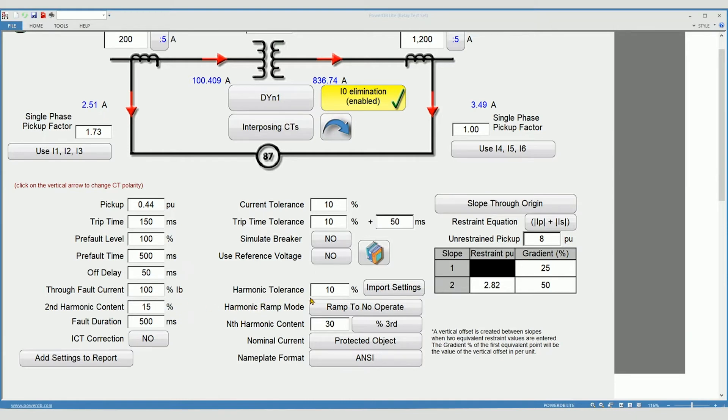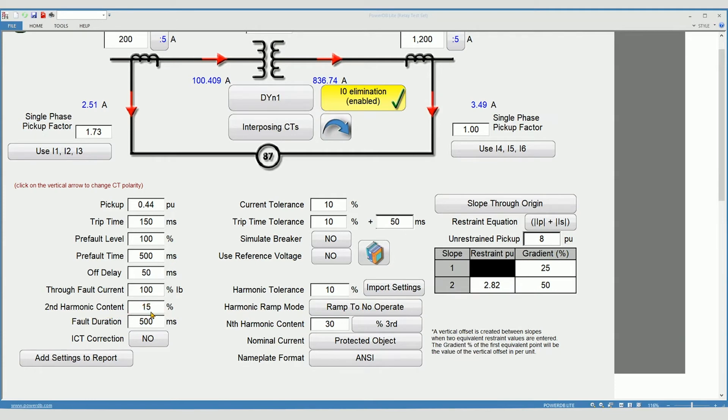Harmonic tolerance. This is the allowable error factor when performing harmonic restraint or harmonic blocking test. Second harmonic content. Enter the setting for your relay for second harmonic restraint or blocking.